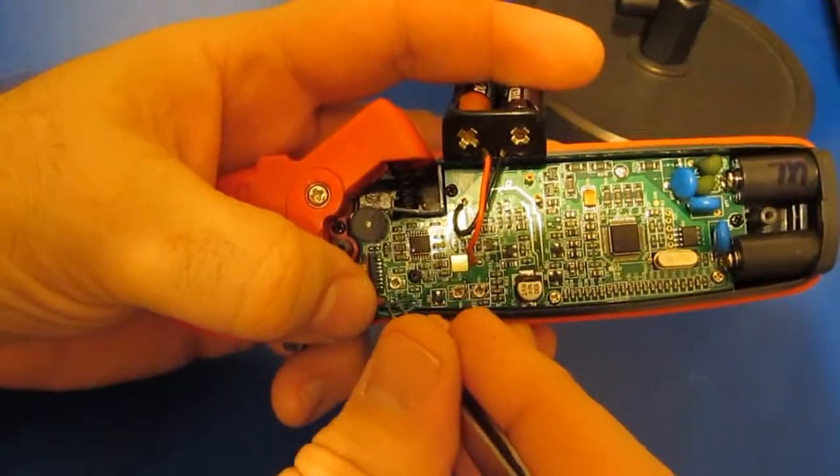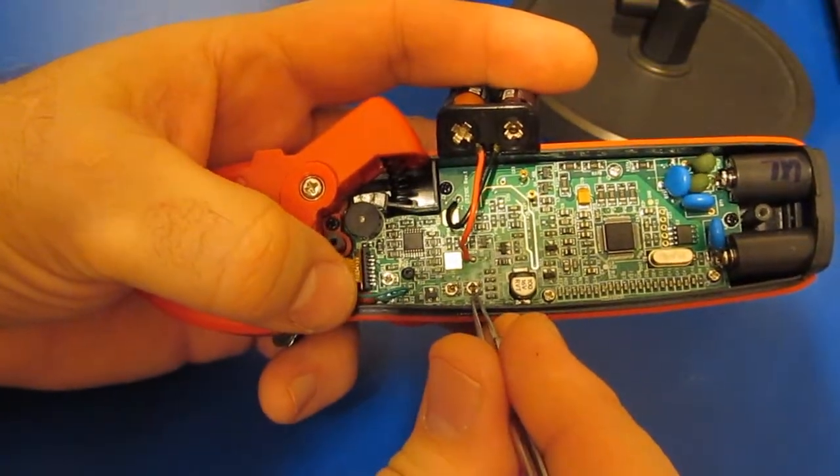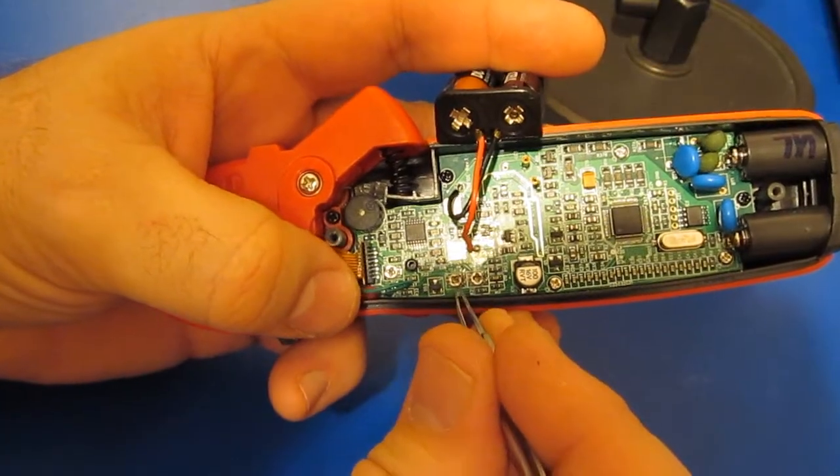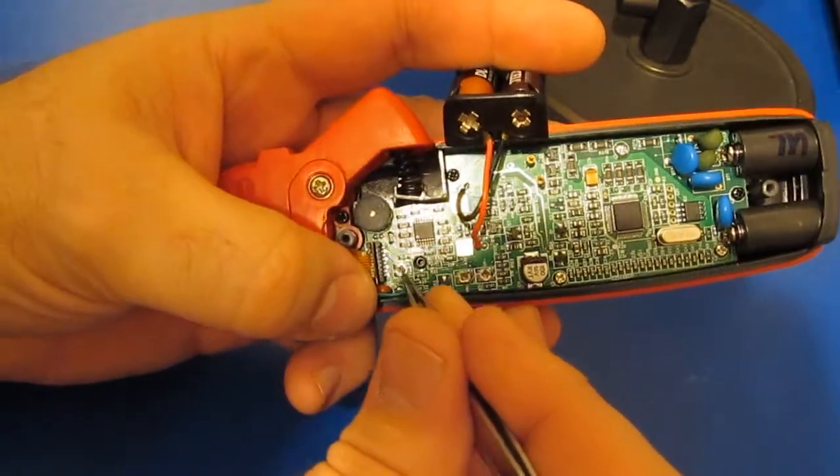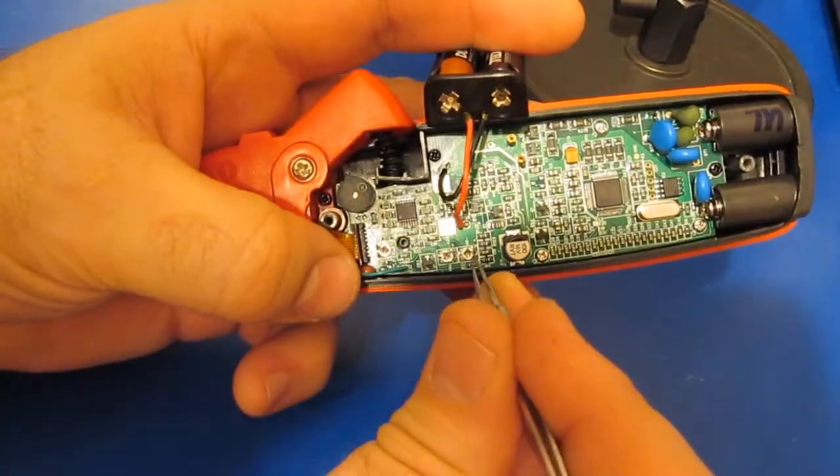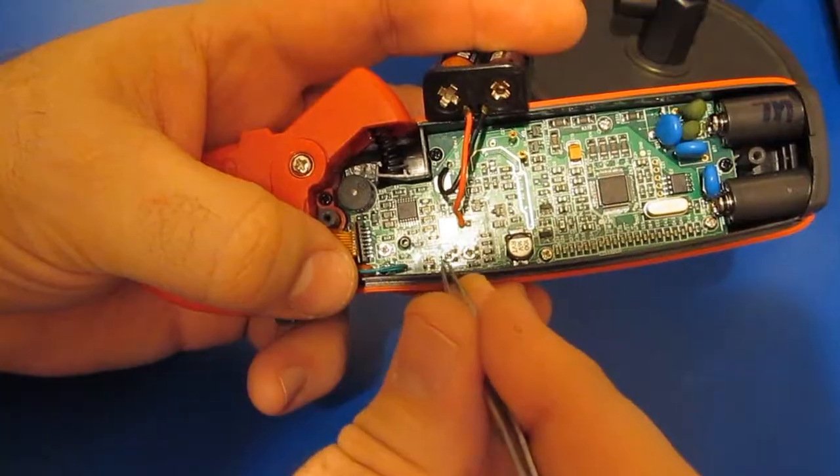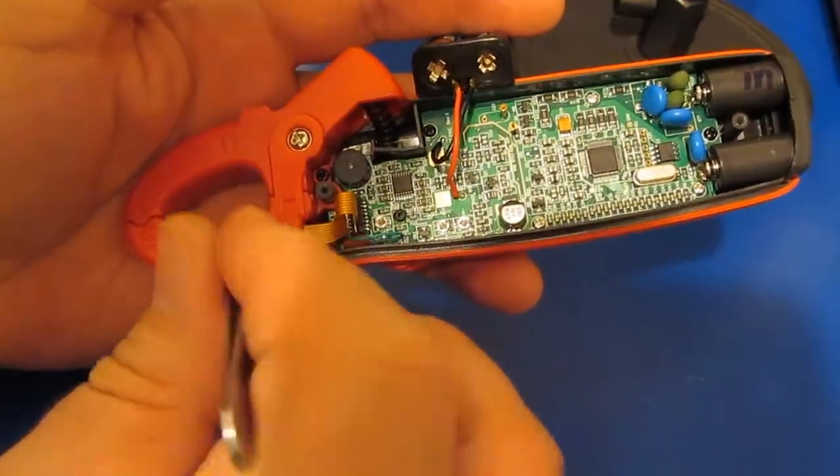Also on the bottom, you notice that there's three potentiometers. There's a VR minus. And then a VR plus. And then VR4. VR minus is the offset adjustment. And then these two potentiometers are setting up the null for the two sensors up in the head.